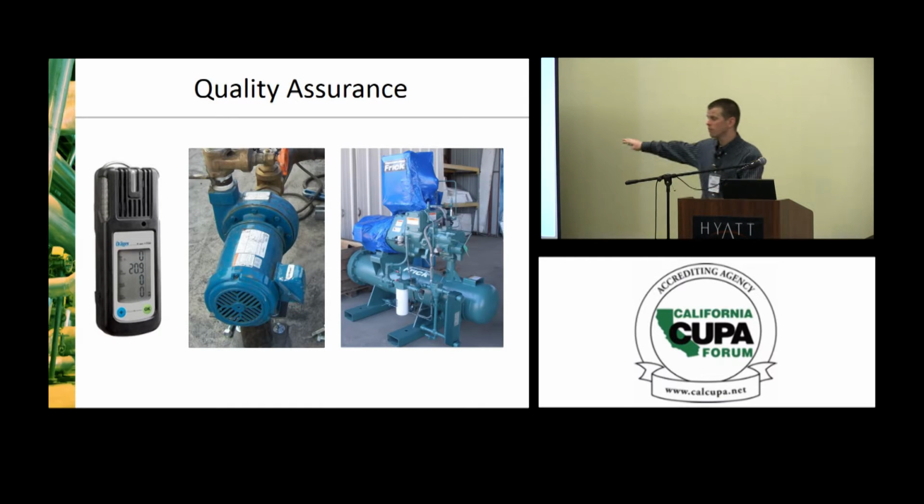We occasionally find a compressor in an ammonia system that says R22. R22 is a freon refrigerant, and usually that just causes us to look further into it, and it's undergone some sort of retrofit, and it's fine. But still, it makes us question the situation. One story I'll share briefly that we ran into, because we were talking about brass and bronze.